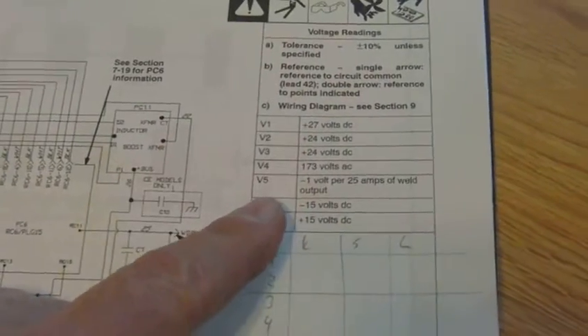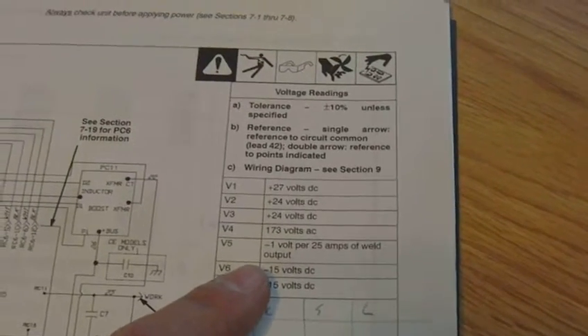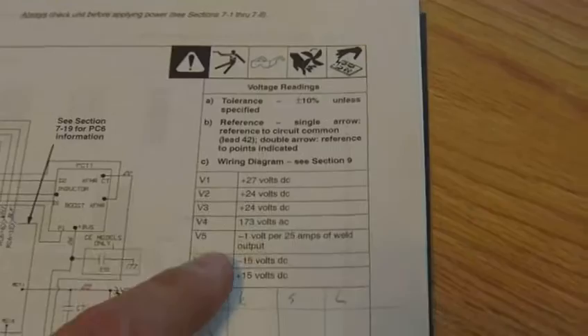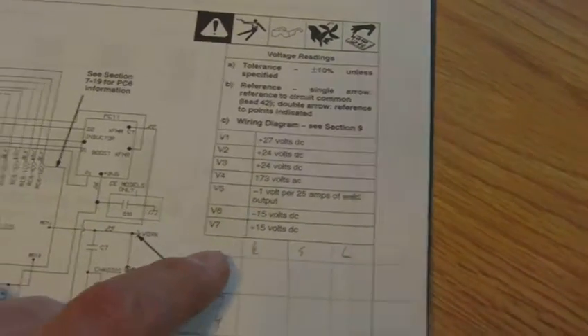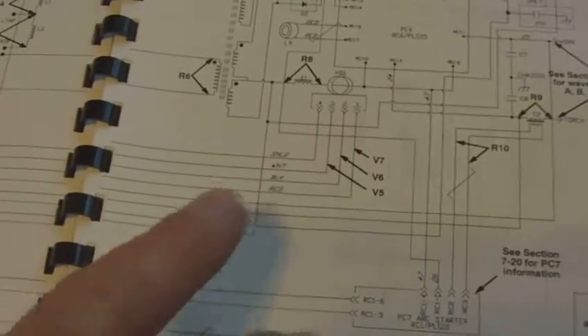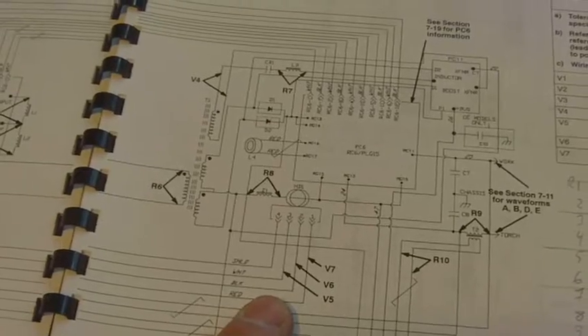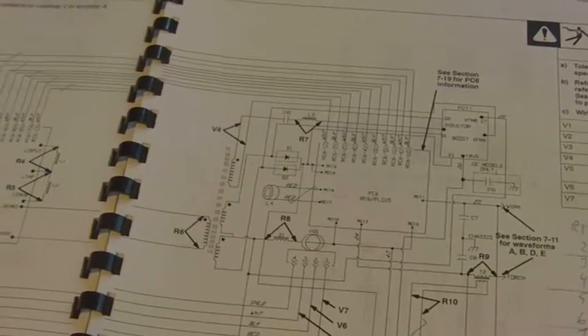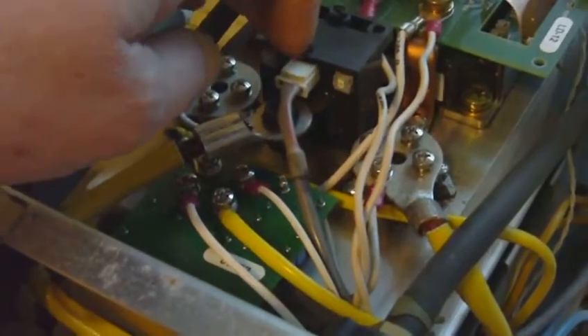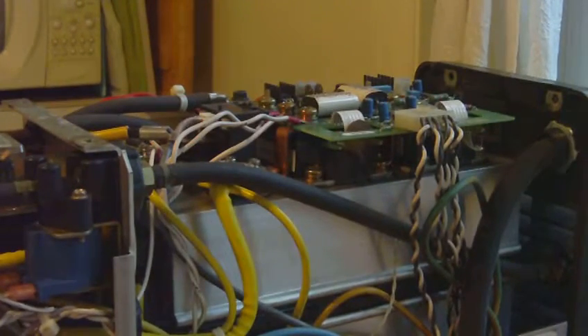V5, I can't actually test on account the display doesn't come on. So I can't set the weld output, which means I can't know what that voltage will be. And V6 and V7 are over here. Where is that? So that is off of... Okay, that's this guy. So here's this Hall device. Comes into this gray one. And that gray one flips around to the other side onto the inverter controller board, which is here.